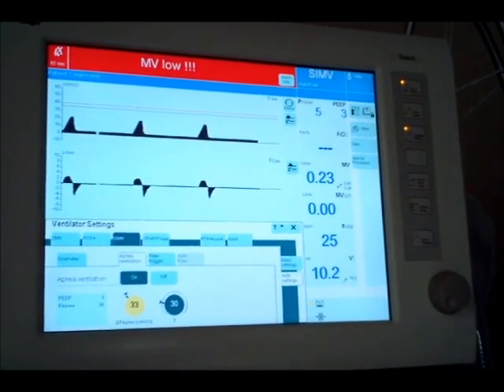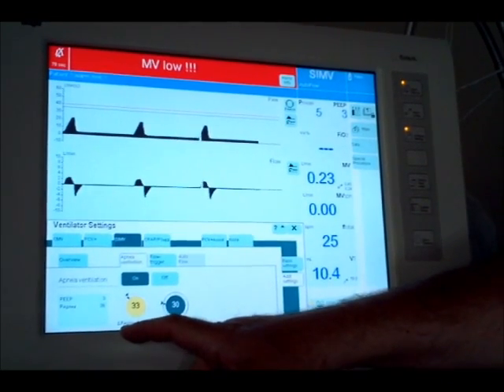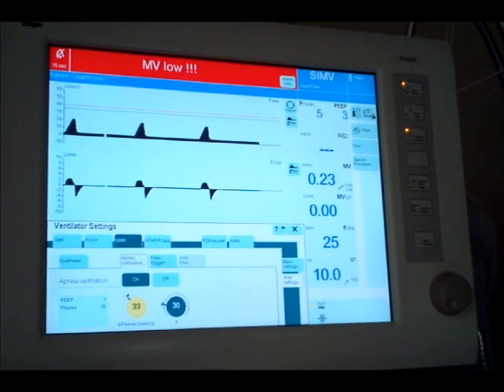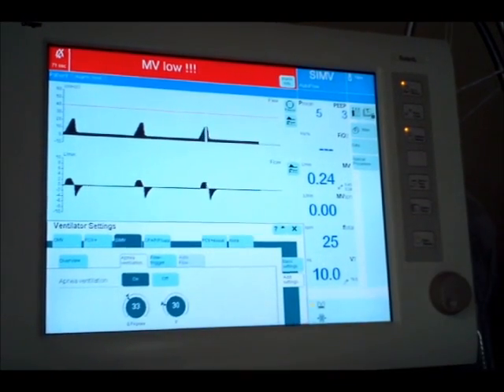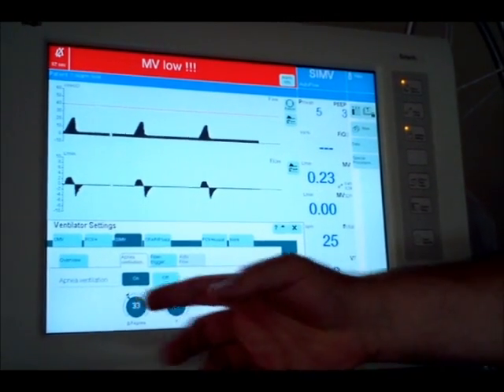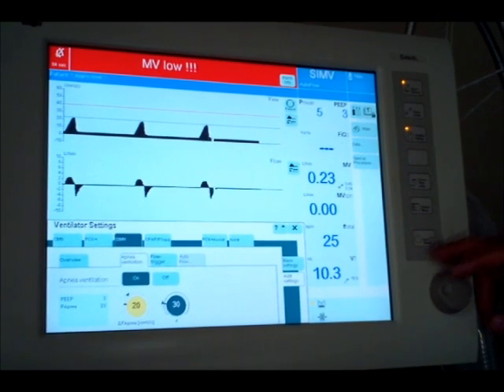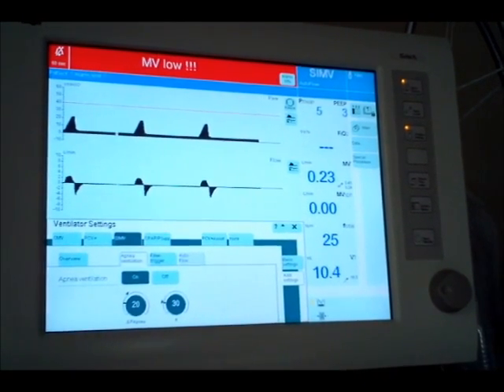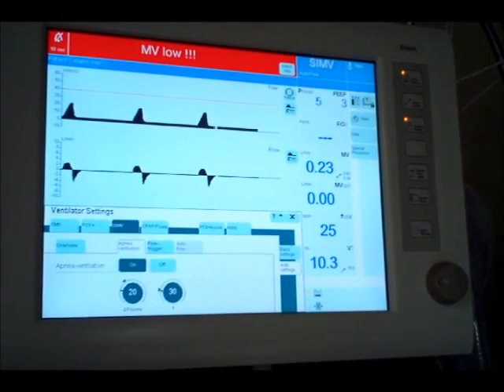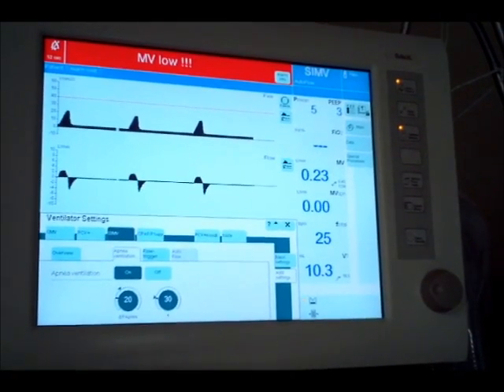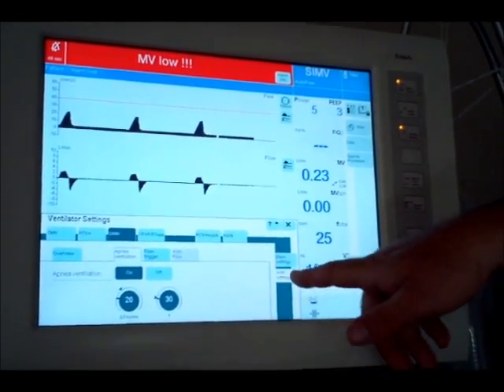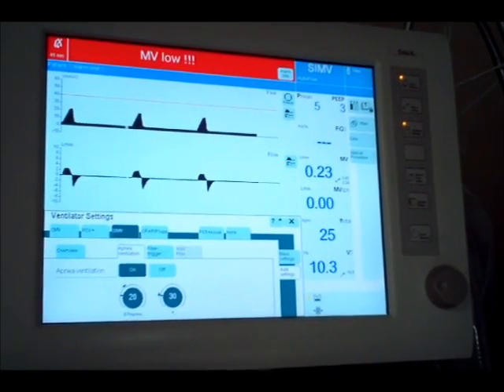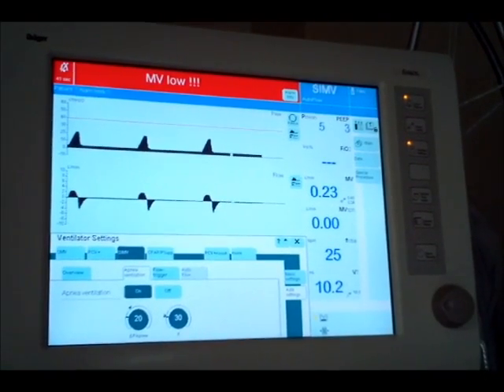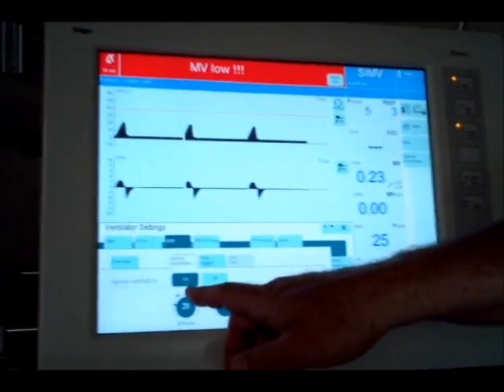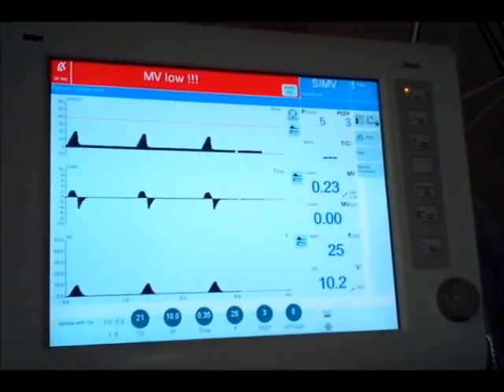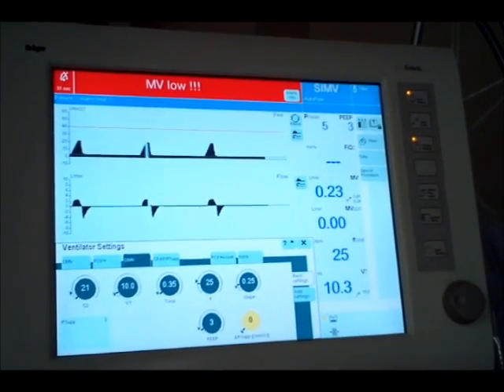Notice this says delta P apnea. So that's going to add it onto the PEEP. My PEEP's 3. If my baby becomes apneic, it's going to give them breaths that are a peak pressure of 36. That's a little bit too high. Let's knock that down to 20. So this is one of those. I'm not going to tell you to set your apnea settings, okay, on that section. You just need to kind of remember it. It might not be a bad idea when you pull up the ventilator settings to make your changes, just think about or look at if there's anything you need to do in that additional settings section. Okay, because that wasn't available before. We're going to leave our apnea settings on. Okay. What do you think of my slope? Good. Good.